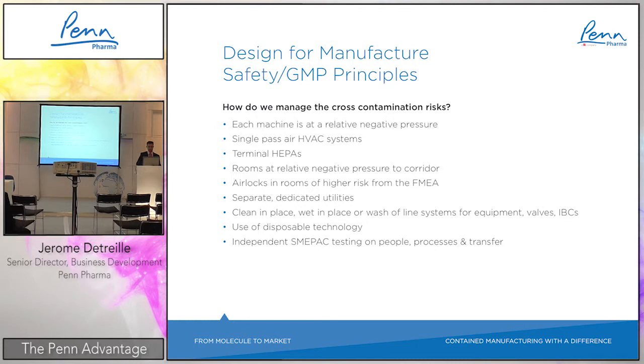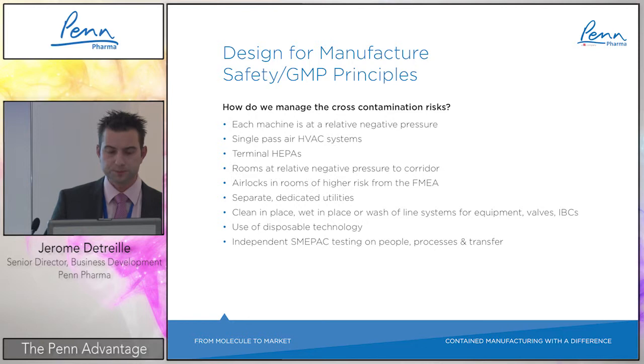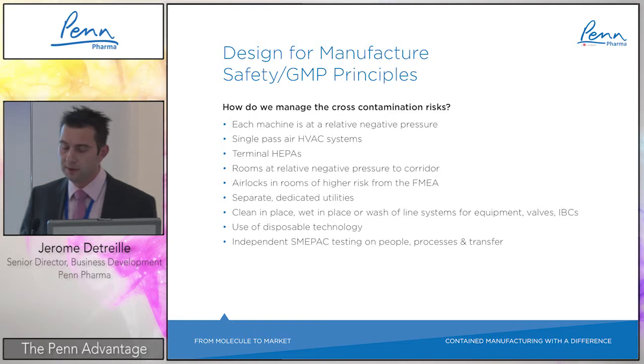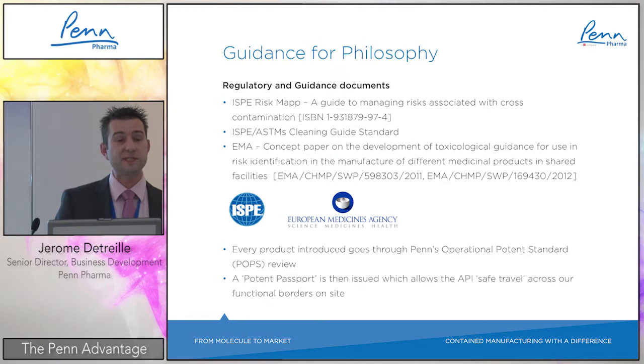Containment valves and IBCs are critical elements. Disposable technology is also used extensively, especially at early stage for development, to speed up the process and enhance flexibility. Fully independent SMEPAC testing is performed to confirm on a regular basis that the 0.01 microgram per cubic meter target is being met. Key guidance followed includes ISPE risk mapping for cross-contamination and ISPE cleaning guide standards.